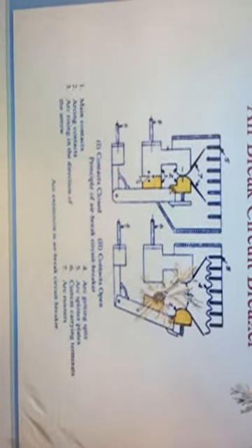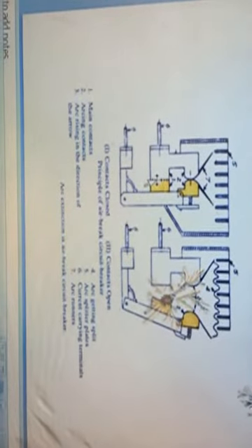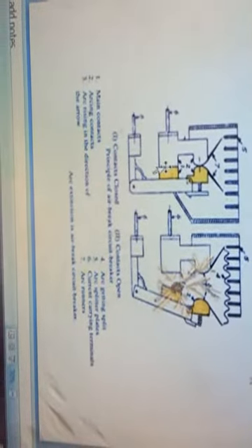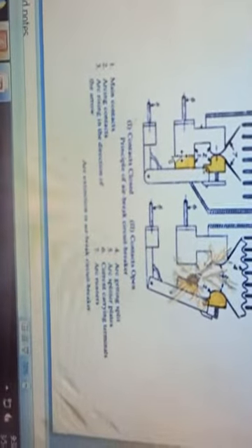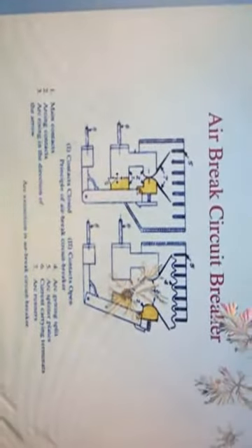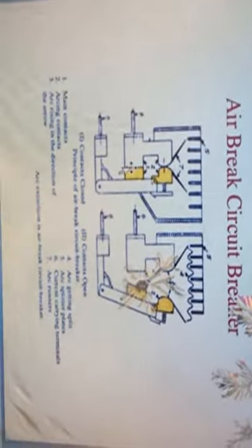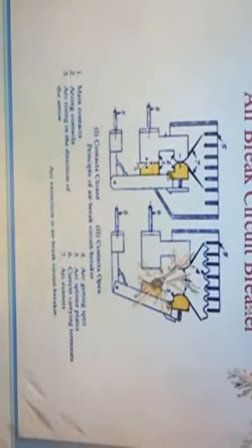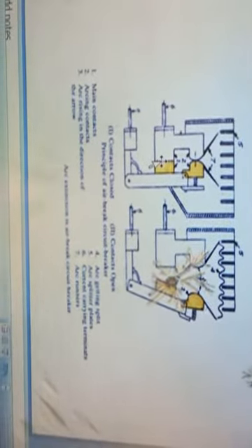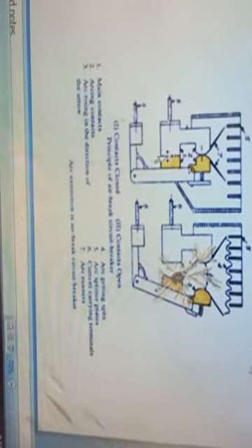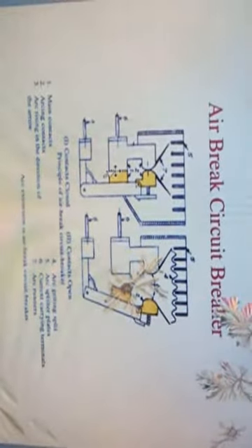The main contact conducts the current in the closed position of the circuit breaker. They have low contact resistance and are silver plated. The arcing contacts are hard, heat resistant and usually of copper alloy. While opening, the main contact dislodges first.